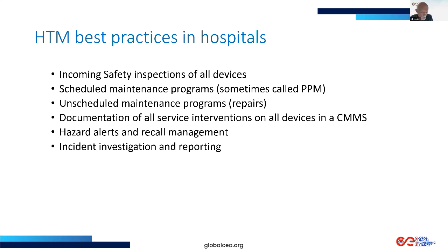They would include the following, which is really just a subset of many other activities we get involved in: incoming safety inspections of all devices, scheduled maintenance programs or PPM, unscheduled maintenance programs or repairs, documentation of all service interventions on all devices in some kind of CMMS, hazard alerts and recall management, incident investigation and reporting. Next slide, please.